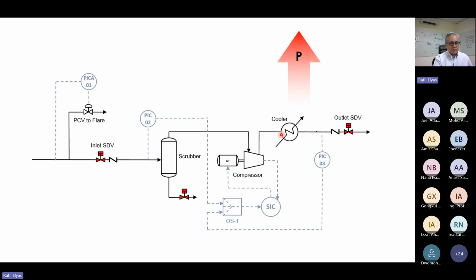So what happens if there's a sudden reduction or retardation in flow? Your pressure goes up. When your pressure goes up, there's a potential for reverse flow. So there's a potential that your gas, rather than going forward, will want to go back. When it goes back, it starts to pressurize your suction, and after the suction gets pressurized, it goes back to the discharge, vice versa. So you'll have this sort of oscillatory flow.